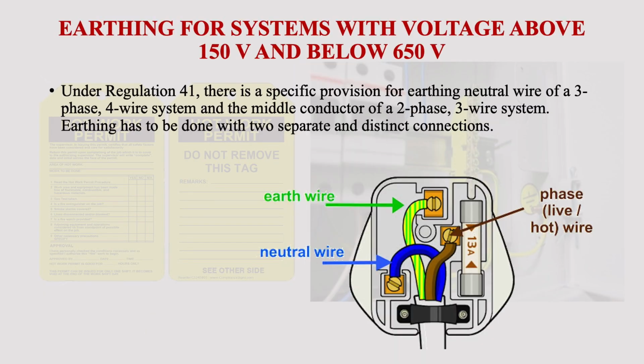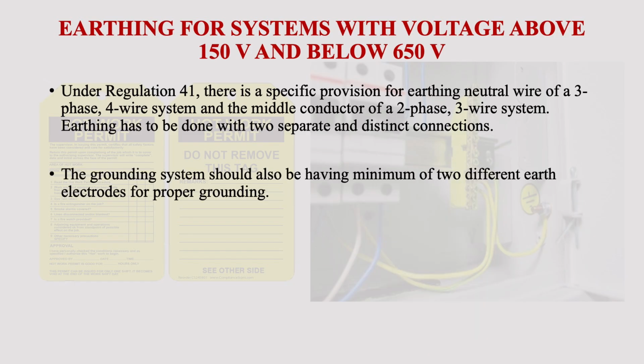Under regulation 41, there is a specific provision for earthing the neutral wire of a 3-phase 4-wire system and the middle conductor of a 2-phase 3-wire system. Earthing has to be done with 2 separate and distinct connections. The grounding system should also have a minimum of 2 different earth electrodes for proper grounding.